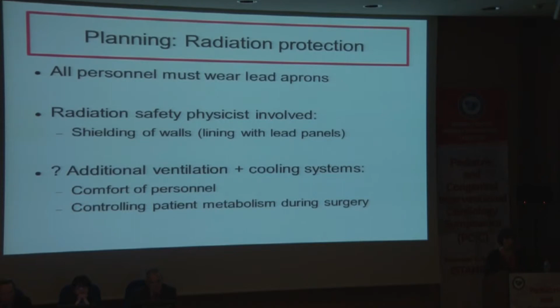Concerning radiation protection, in your hybrid lab, obviously everybody has to wear lead aprons, and not all the staff are used to wearing lead aprons. One should involve a radiation safety physicist to define which walls need to be shielded. And what is important in this sense is to have good temperature control, because often if your walls are shielded, you will have higher temperature in your units, and your cooling systems often have to be adapted. One, for the comfort of the personnel, because it's often long procedures and the surgeons usually aren't used to working under those conditions. And secondly, for the patient, because surgeons also prefer lower temperatures for the metabolism of the patient during cardiac surgery.